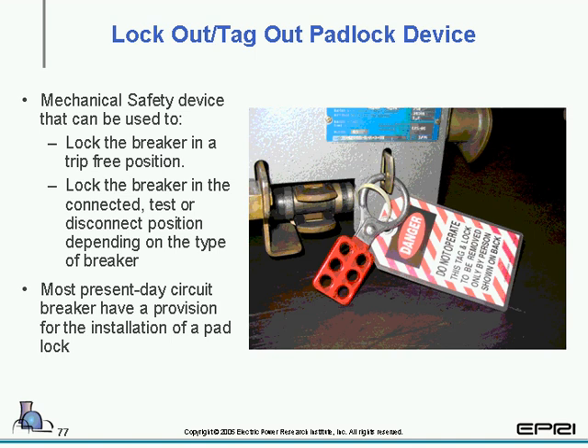We have lockout, tagout, padlock devices, which are mechanical safety devices that can be used to lock the breaker in a trip-free position or lock the breaker in a connect, test, or disconnect position depending upon the type of breaker. And most present-day circuit breakers provide a provision for installing a lockout hasp. Older design breakers, pre the 70s, may not provide a lockout hasp or a way to install one.